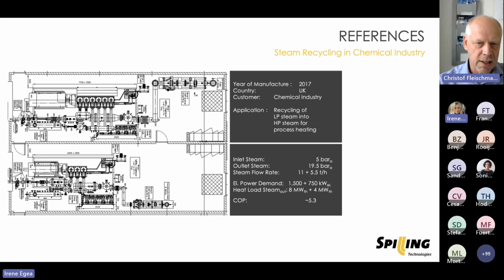For the full available low pressure steam flow here of 16 tons, 2 units are necessary: 1 6-cylinder unit, which manages about 11 tons per hour, and a smaller 3-cylinder unit for about 5.5 tons per hour.